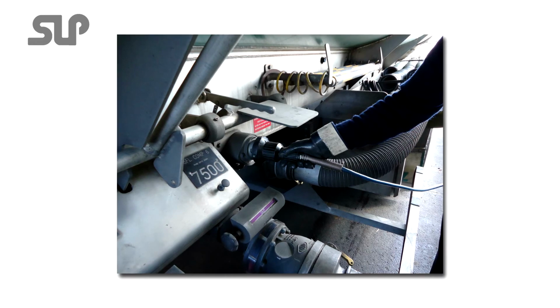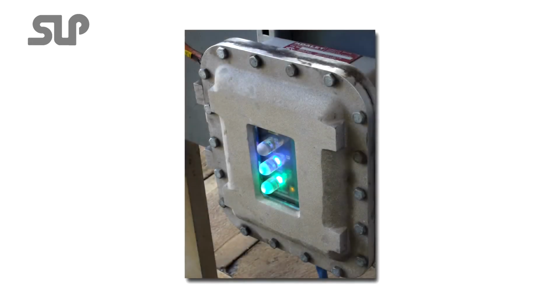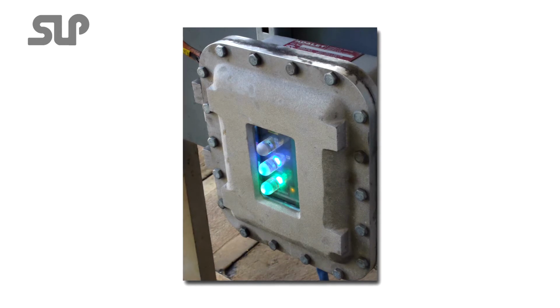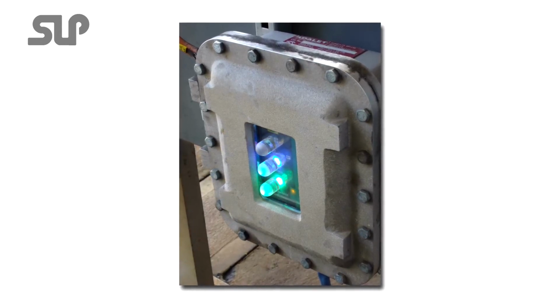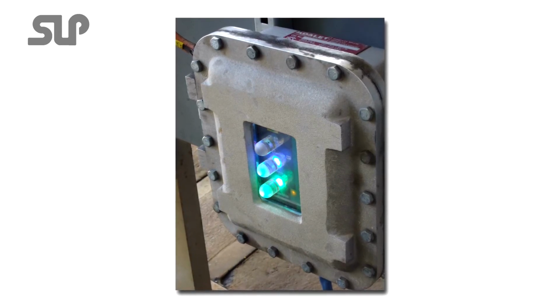Step 6. Connecting the gantry overfill protection system to your tanker creates an electrical bond between your tanker and the gantry, allowing static electricity to equalize between the gantry and your tanker. The overfill protection system is a self-checking system and will only generate a green light to load if an electrical bond between your tanker and the gantry has been made.